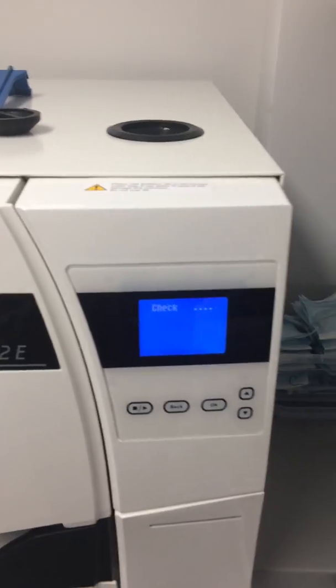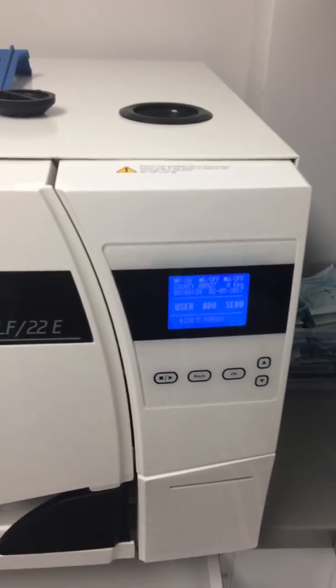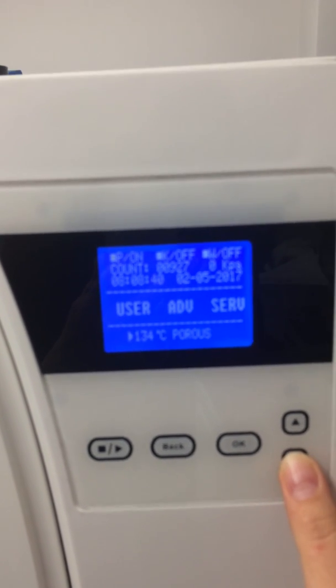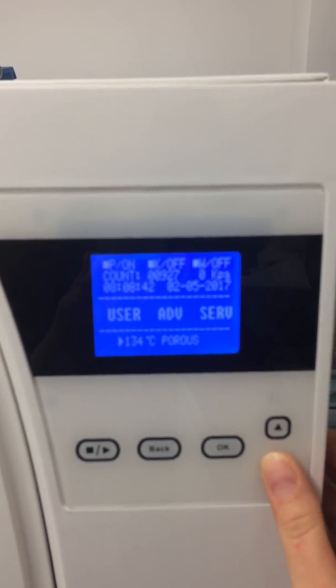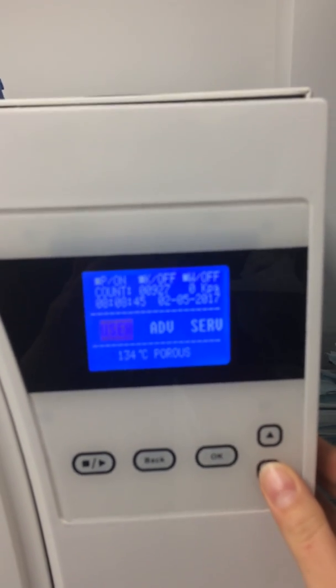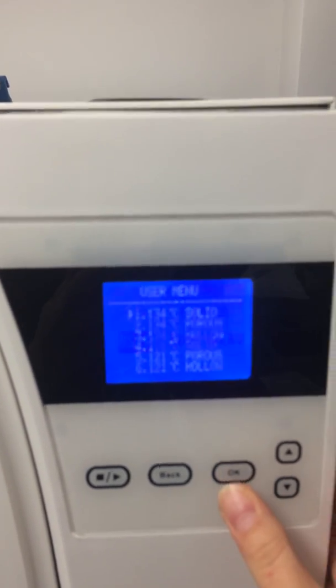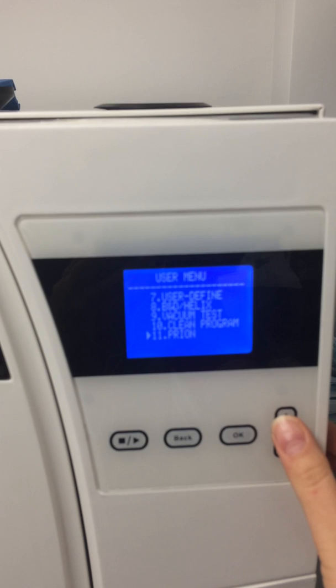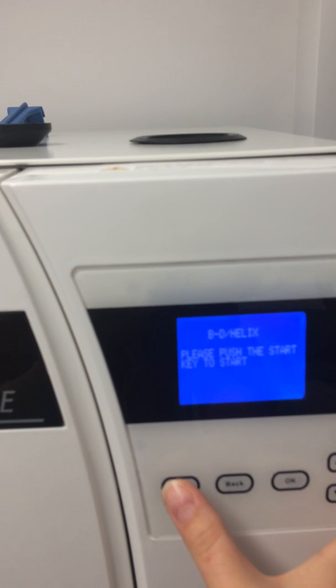and then on the side you can see there is a green button. We open, we start the autoclave, and then we go to the menu. To go through the menu we use the up and down buttons. User, okay, and then I go and find the Bowie-Dick Helix test. It's number 8. Then I push OK, and to start I just use the start button.